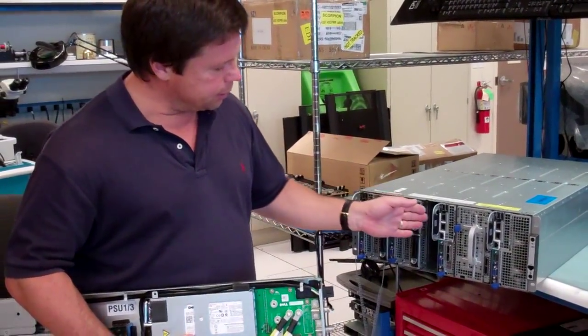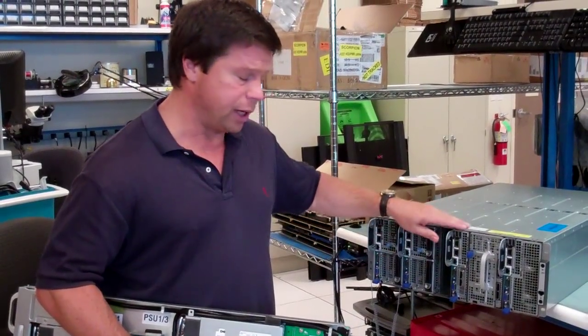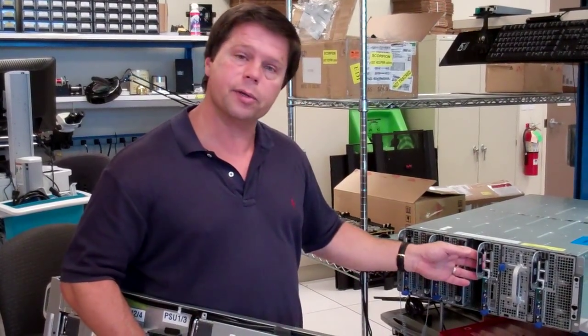You could have, in addition to 2,800 watts, another 2,800 watts. So fundamentally, it's a 1+1 of 2,800 watts when you look at the serviceability side of it — that's if you want the redundancy.